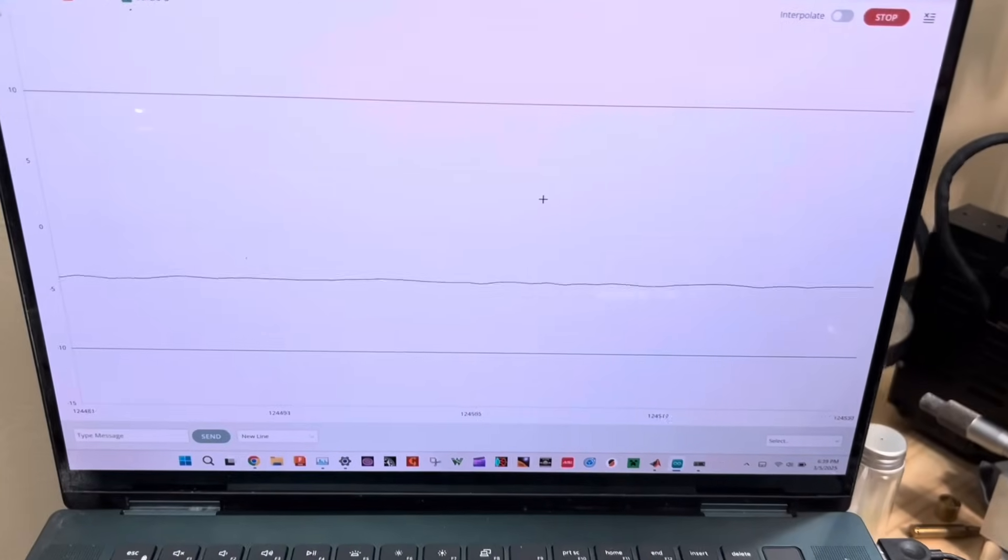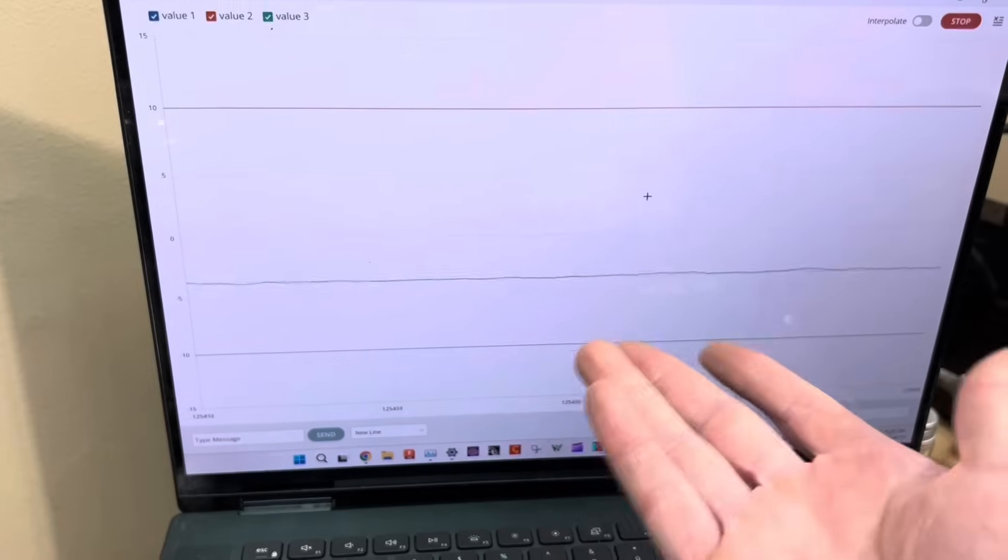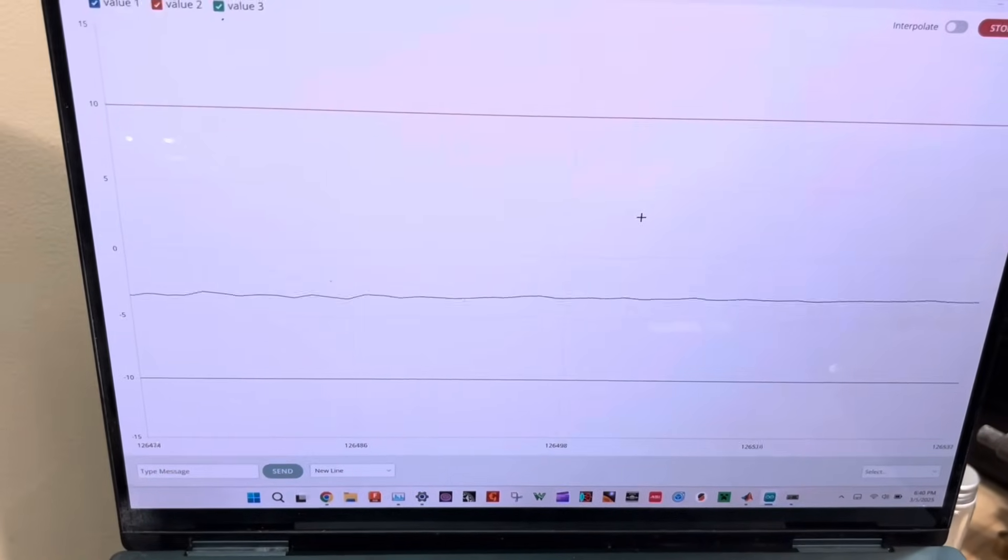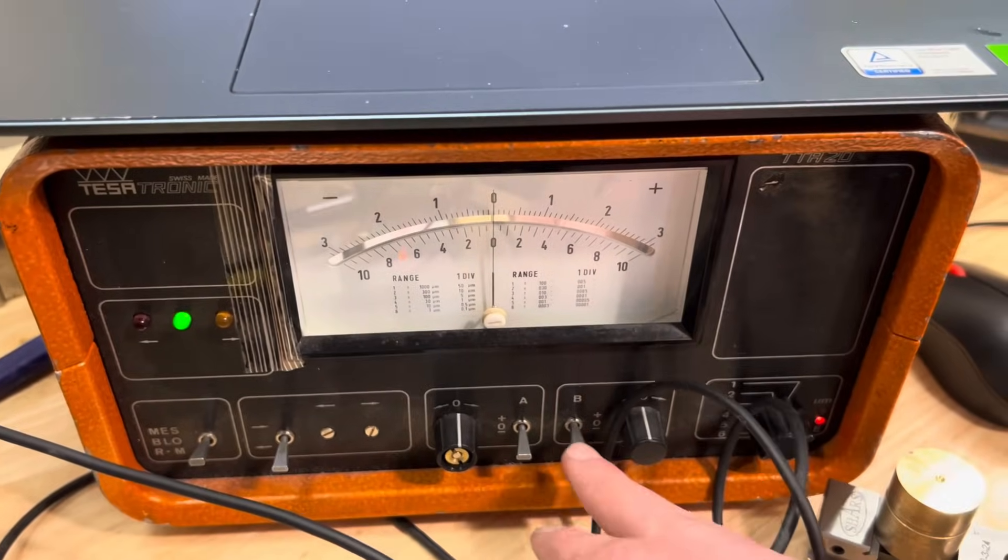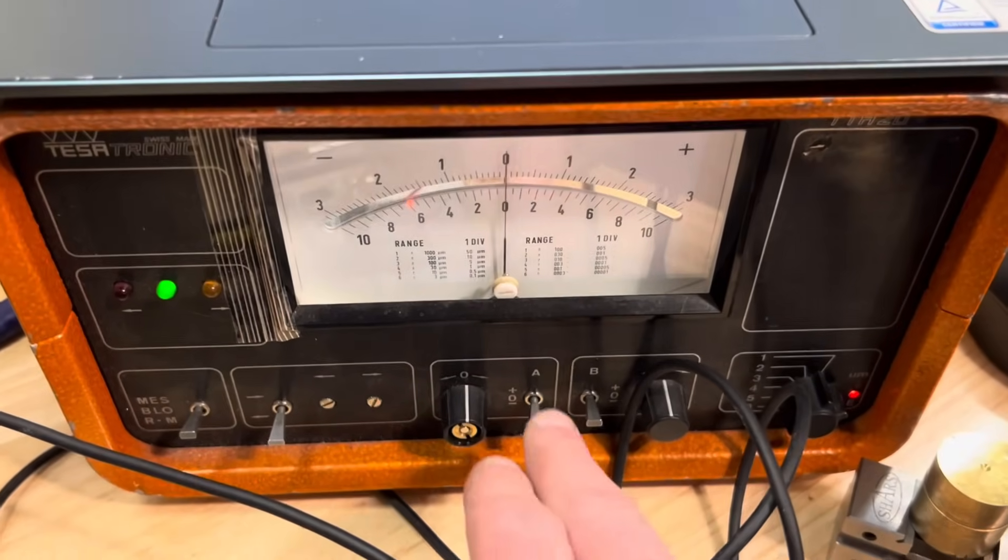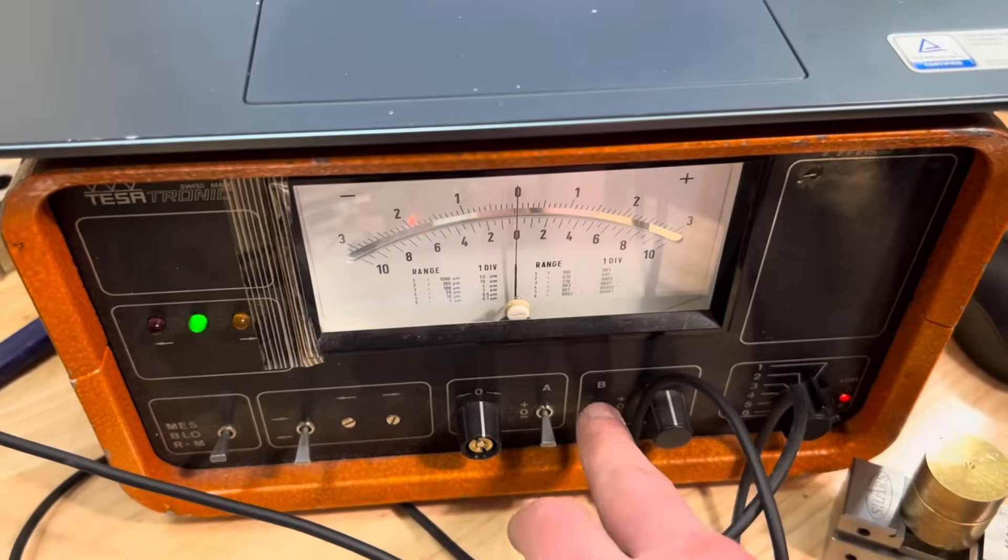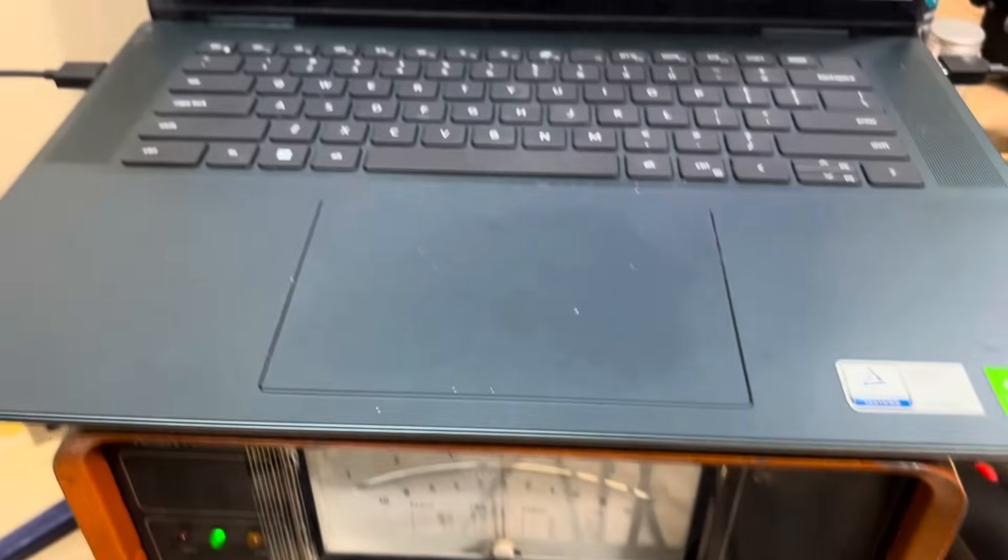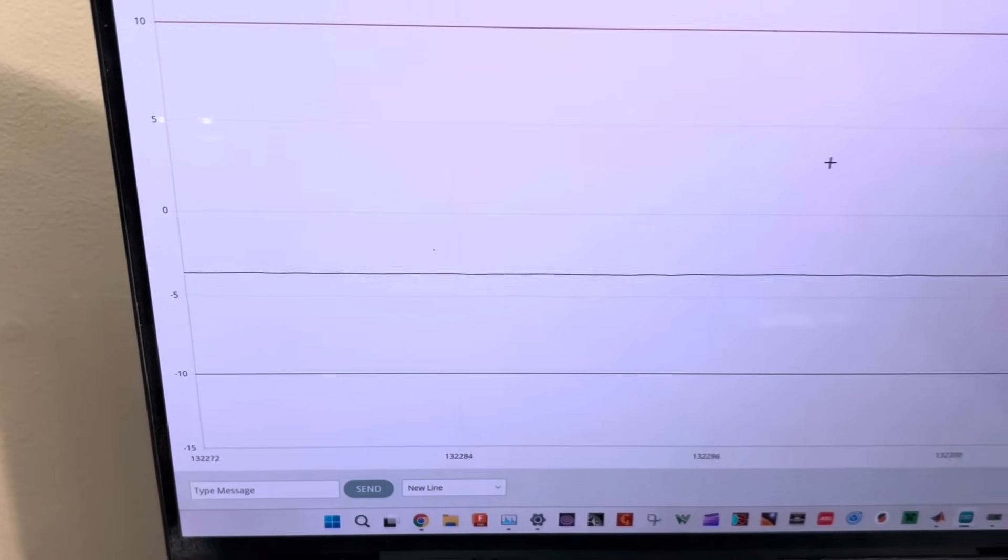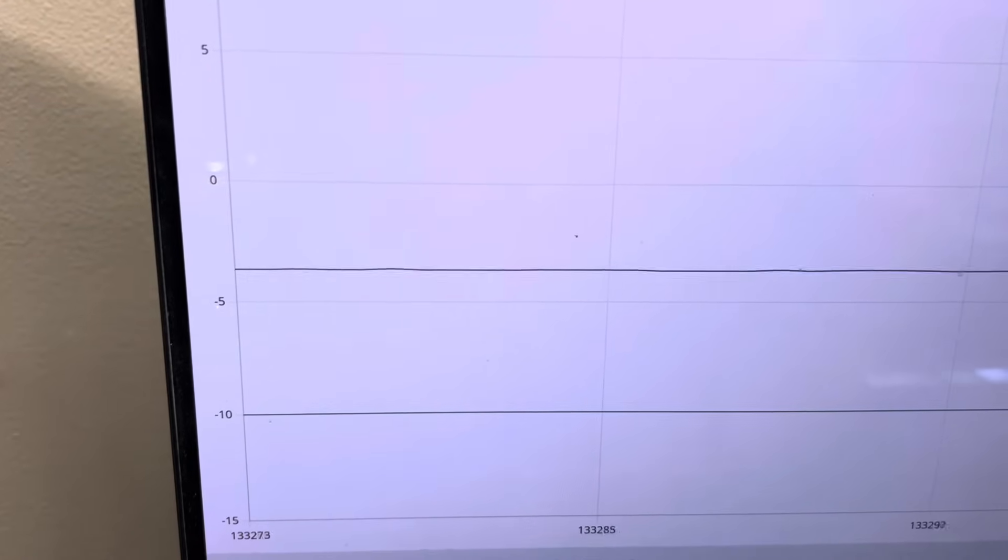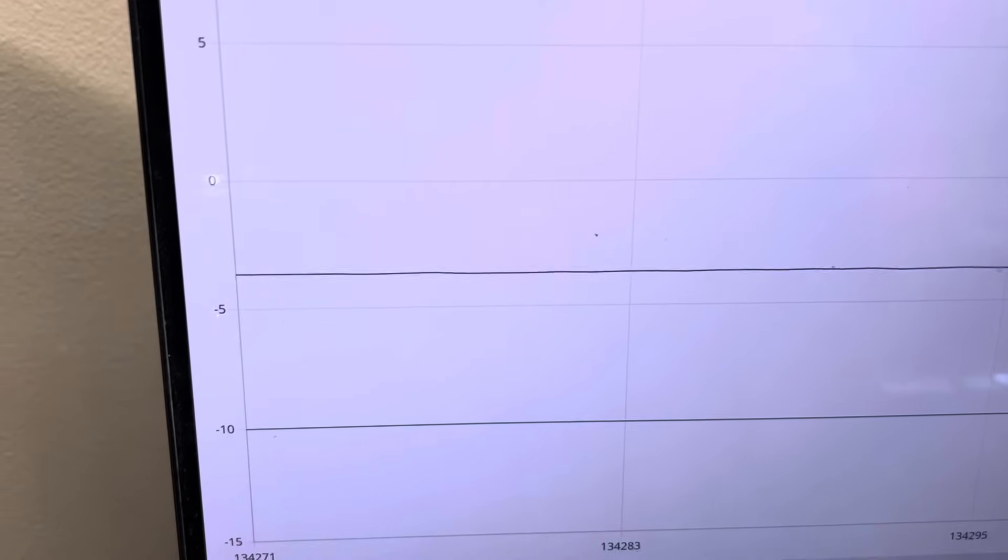And just to interject here, I'm sure I'll maybe still get some comments about it possibly being electrical noise at this point. Just to sort of demonstrate that there is still a mechanical noise floor here. I can turn the input to my amplifier off. So right now when I poke the gauge, it's responding. But if I set it to zero, we're no longer reading from channel B or channel A. And it defaults to zero, of course. And so now the analog output is really just anything we're seeing here is not mechanical. This is just the electrical noise floor of the instrument. And that's certainly smaller than what we're seeing normally.